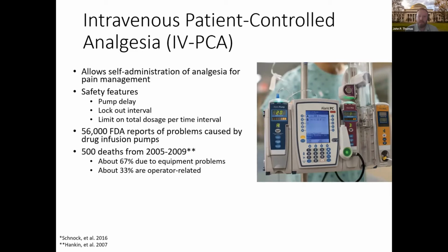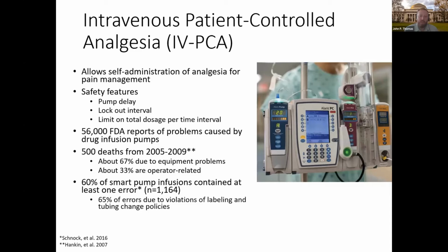A study was done of these smart pump infusions in hospitals, and they found that 60% of them contained at least one error, and a lot of them contained multiple errors. Of those errors, 65% involved violations of labeling and tubing change policies, very preventable, or you would think they would be preventable types of things. 87 of these infusion pumps had to be recalled because there were safety issues that were not anticipated when they were designed and assessed and approved.